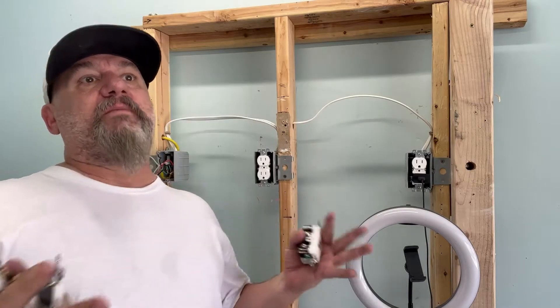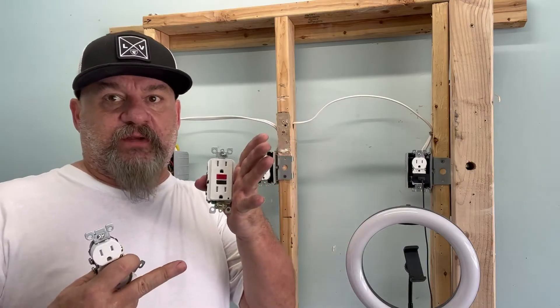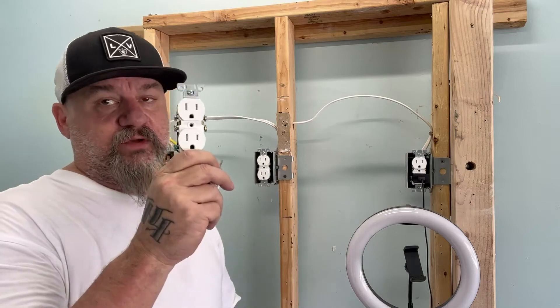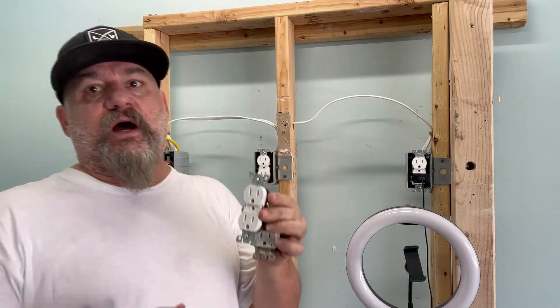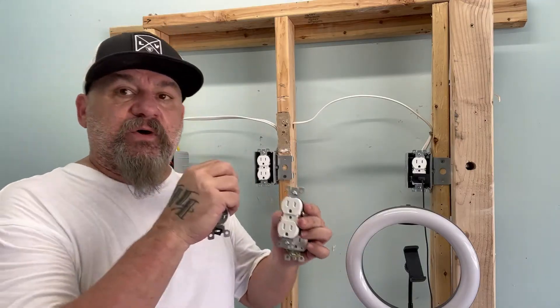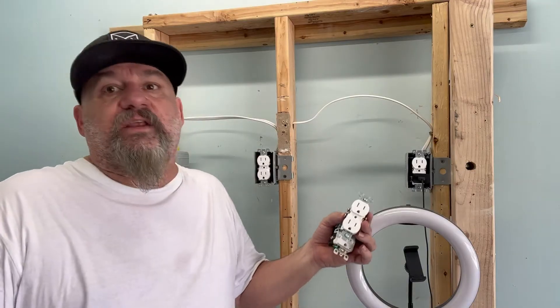Now the problem is how do we know where to put our GFI receptacle? It has to protect that whole circuit in order to put ungrounded receptacles in. When you do, the GFI receptacles come with little stickers that say 'GFCI protected circuit.' You have to put them on each outlet so the inspector knows.